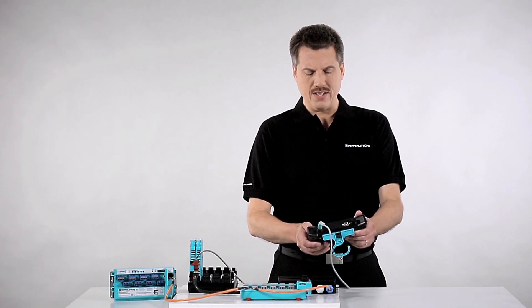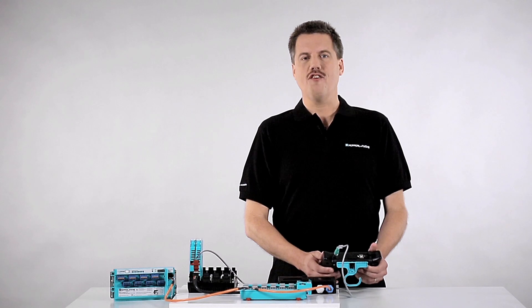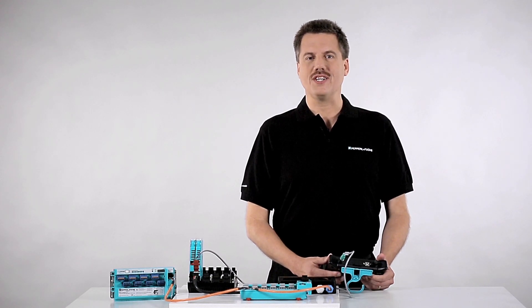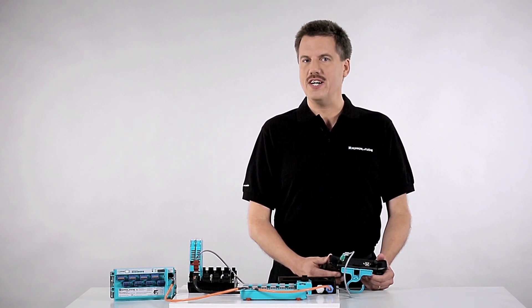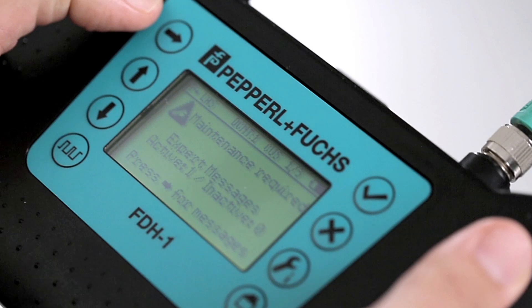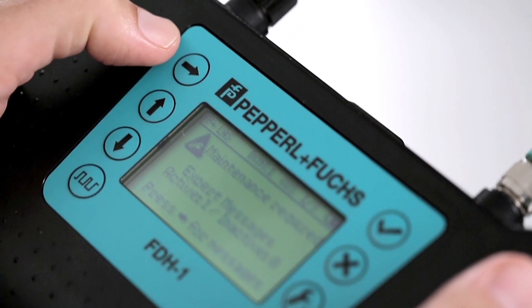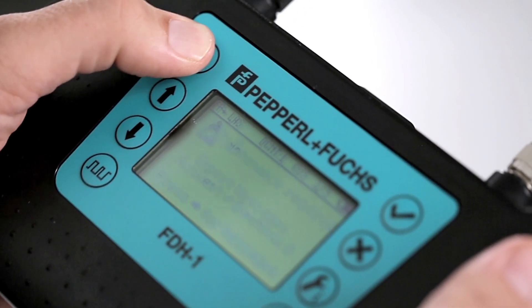Maintenance required. Our field bus segment here appears to be operating at suboptimal levels, so let's find out. The button with the right pointing arrow allows me to access the phenomena detected.